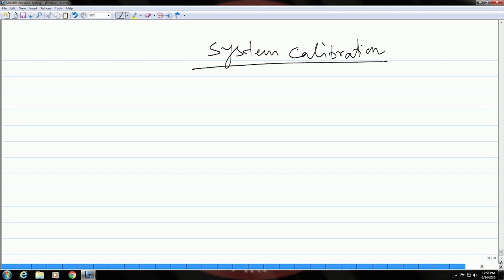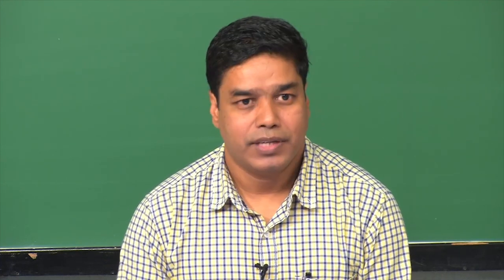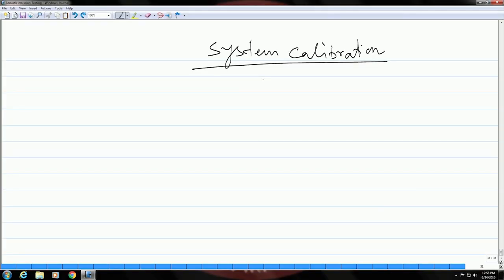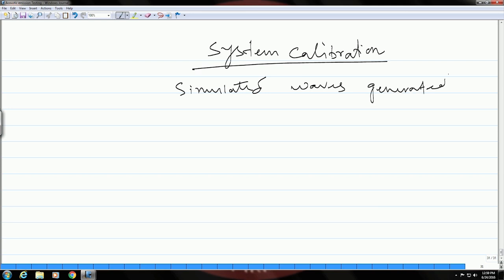In order to calibrate a system, you need to have some reference which could generate a signal that can be used as a defect signal and calibrate the instrument. In this case you need to simulate acoustic waves which come out from defects using a pulse generator which can simulate acoustic emission from actual emission events.